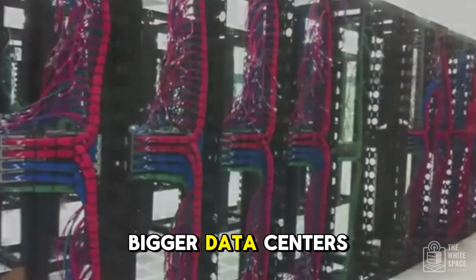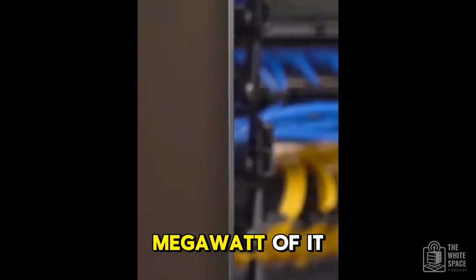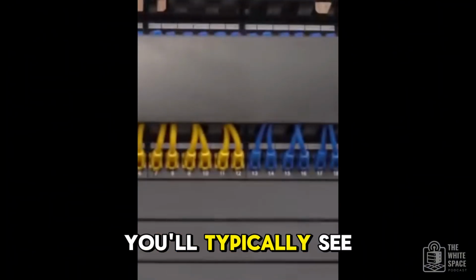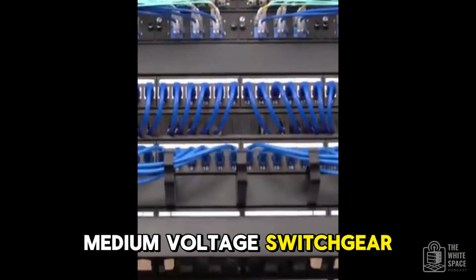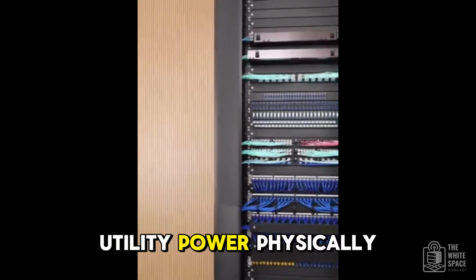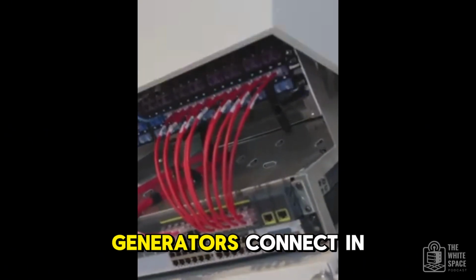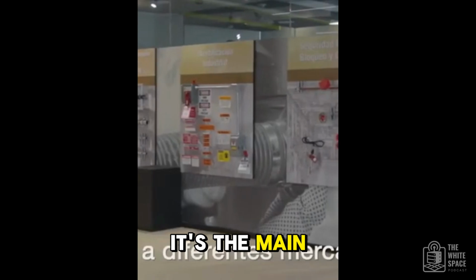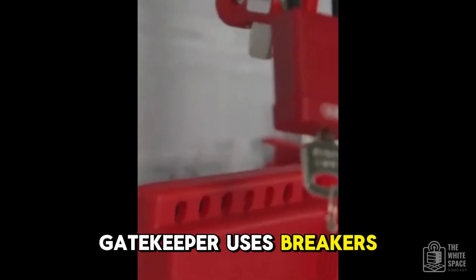Now, for the bigger data centers, say over 1 megawatt of IT load, you'll typically see medium voltage switchgear, MV switchgear. That's where the utility power physically enters and where the generators connect in—it's the main gatekeeper, using breakers, fuses, and meters to protect everything downstream.